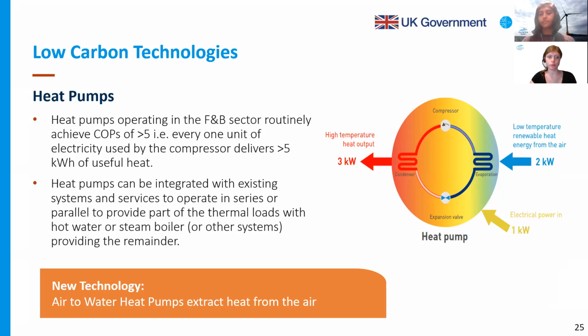Specifically, when you want to generate hot water, your hot water boiler can be offset with the use of heat pumps. Some of the potential waste heat streams you could consider for upgrading with heat pumps are heat rejected from chillers, refrigeration systems, dryers, or other wastewater streams. Even in your wastewater treatment plants, if you have heat, that can also be recovered using a heat pump and delivered to a higher quality temperature heat requirement.